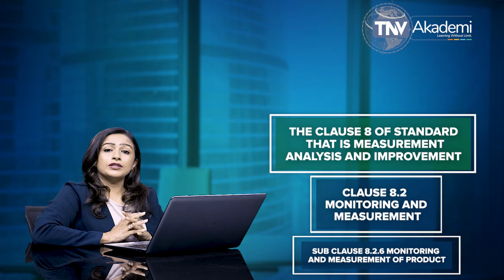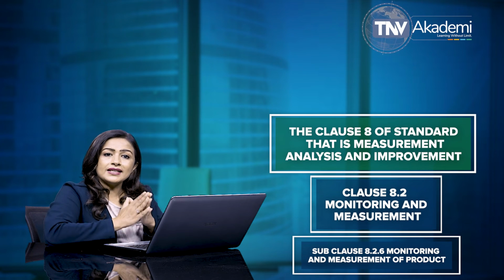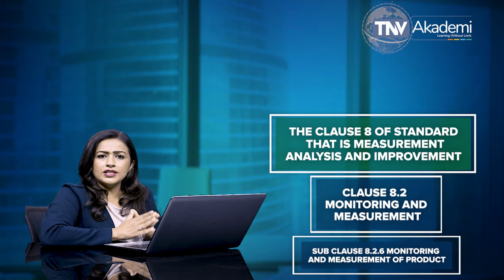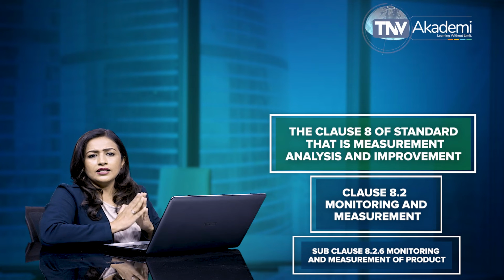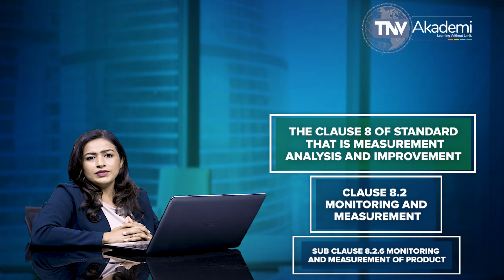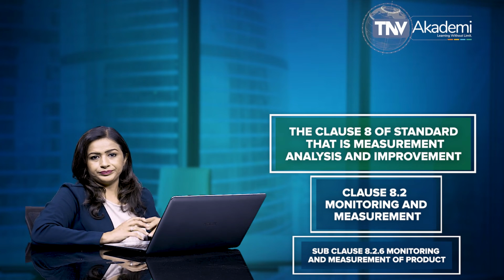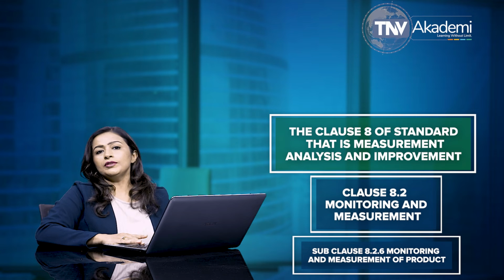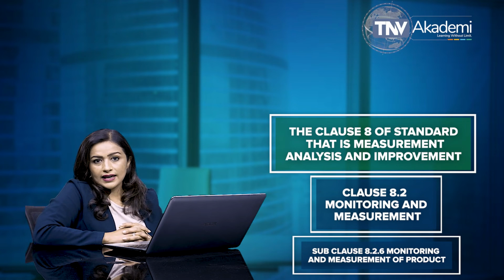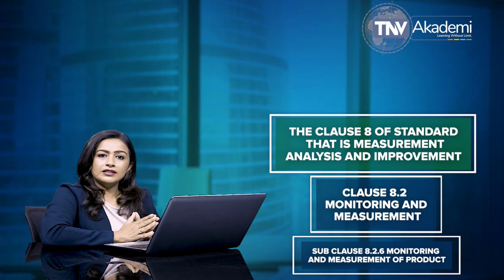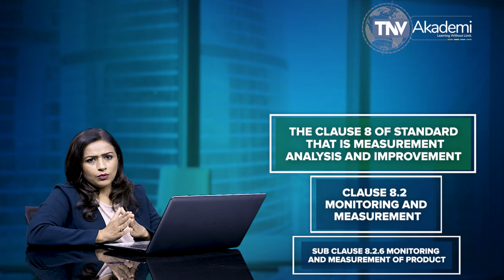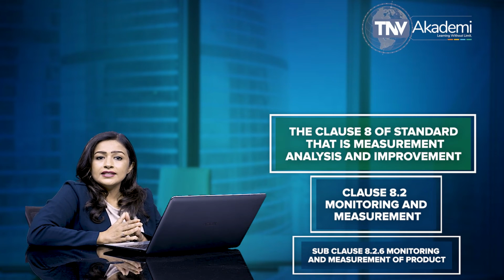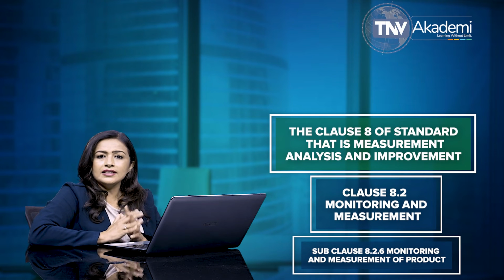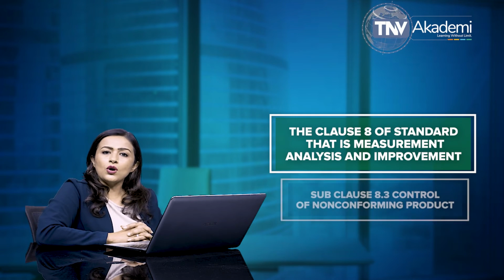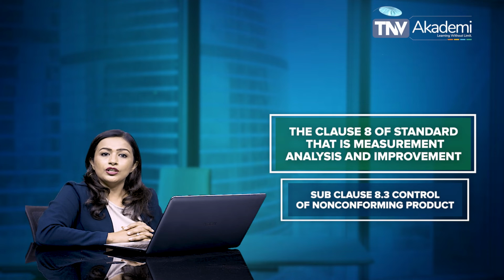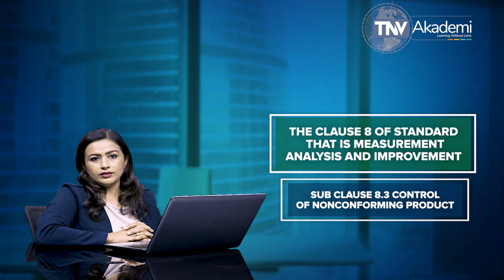Further, as per this standard, the product release and service delivery must not proceed until the planned and documented arrangements have been satisfactorily completed. The subclause 8.2.6 states that for implantable medical devices, the organization is required to record the identity of personnel performing any inspection or testing. Let us talk about subclause 8.3, control of non-conforming product.